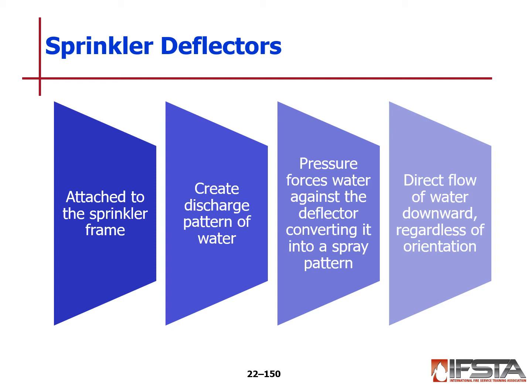Your deflectors are attached to the frame of the sprinkler. They create a pattern of discharge, a pattern of water, if you will, depending on how they're shaped. The pressure forces water up against the deflector, converting it into that spray or pattern. The direct flow of water downward, regardless of its orientation, the deflector will spread it out in the proper pattern.